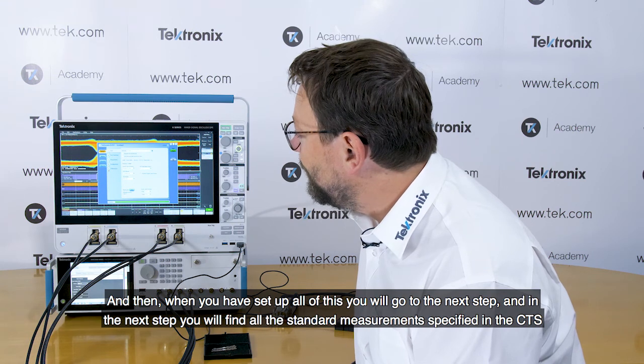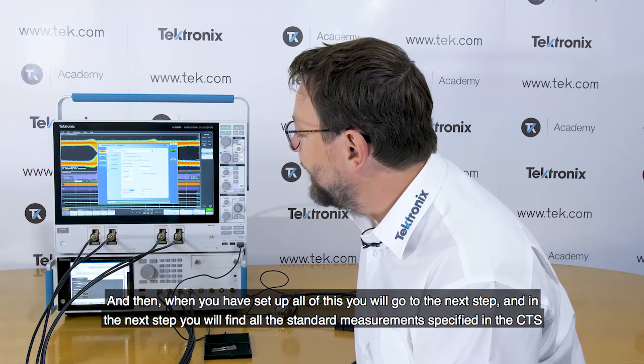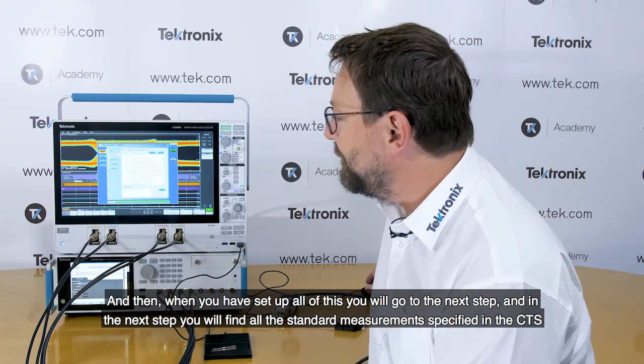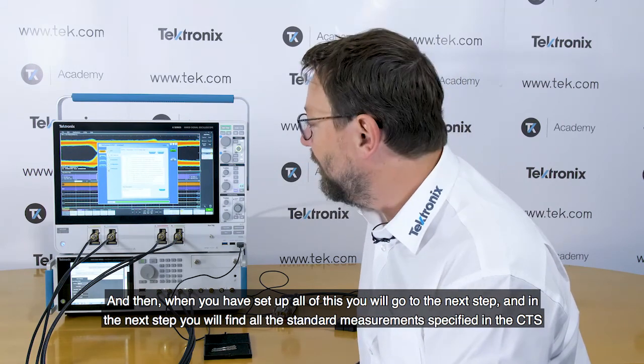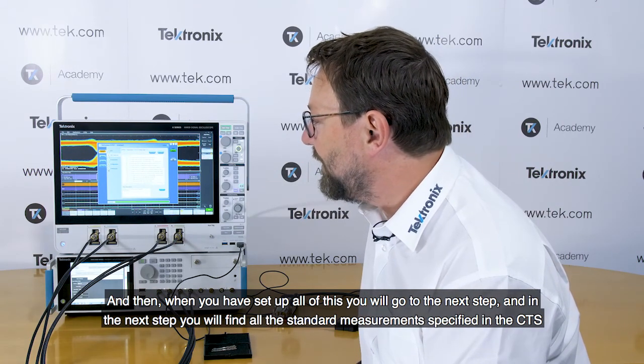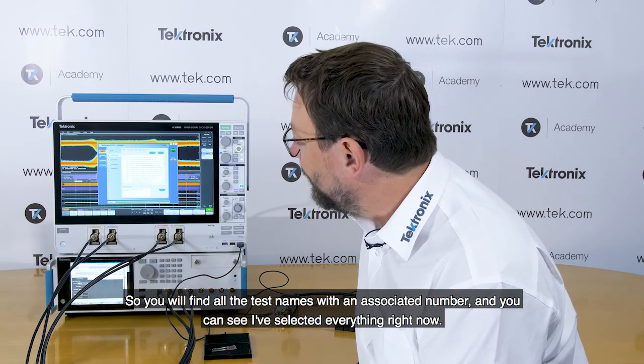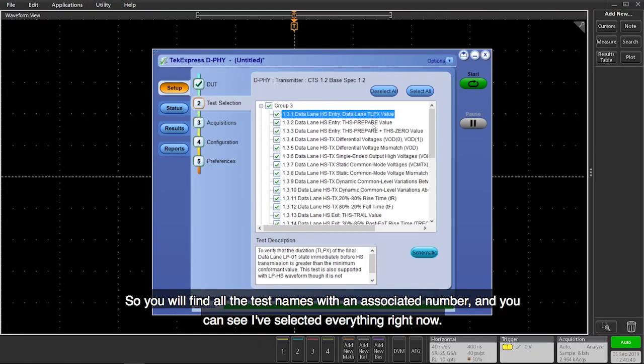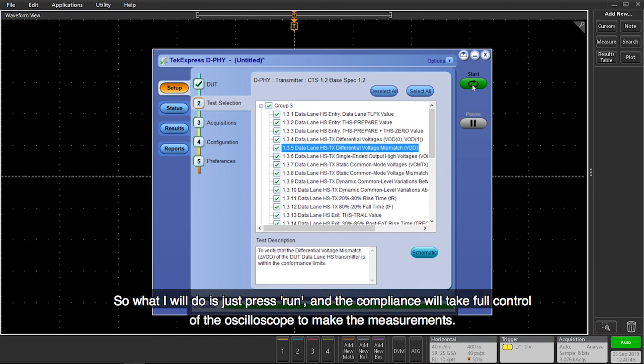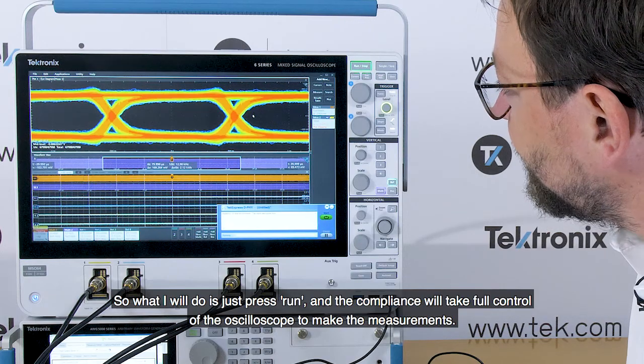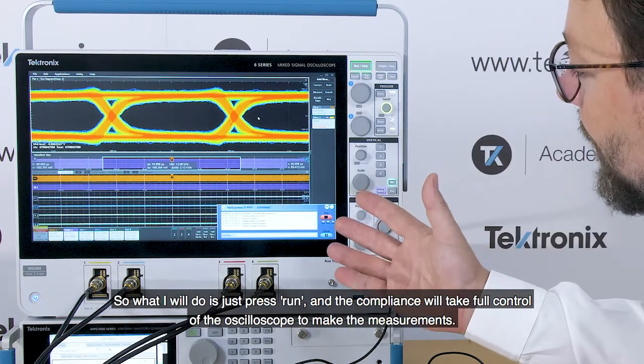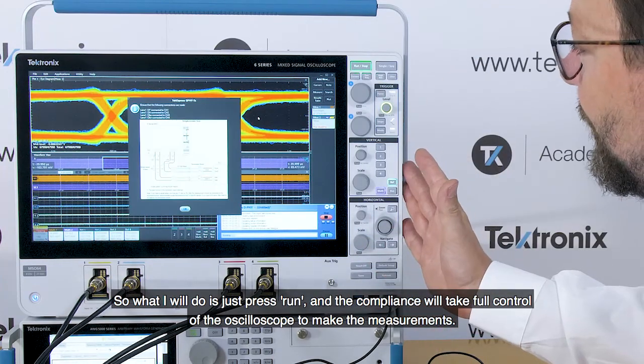And then when you will have set up all of this, you will go to the next step. And in the next step, you will find all the standard measurements specified in the CTS for MIPI DPHY. So you will find all the test names and associated number. And you can see I've selected everything right now.